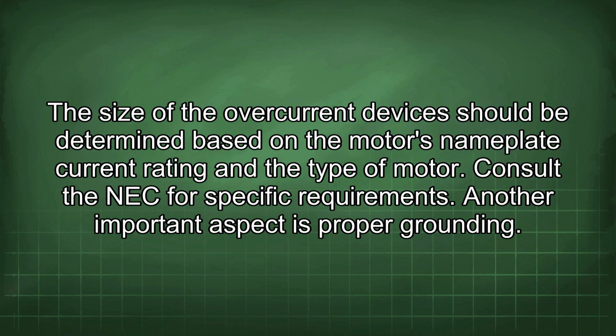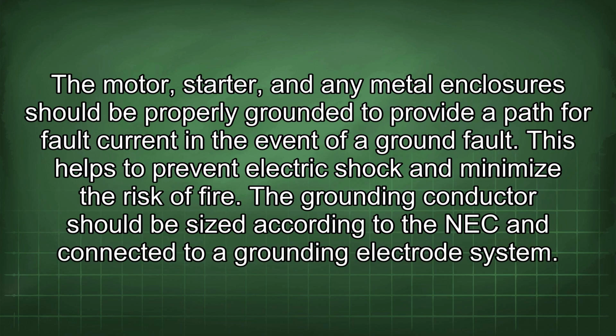Another important aspect is proper grounding. The motor, starter, and any metal enclosures should be properly grounded to provide a path for fault current in the event of a ground fault. This helps to prevent electric shock and minimize the risk of fire. The grounding conductor should be sized according to the NEC and connected to a grounding electrode system.